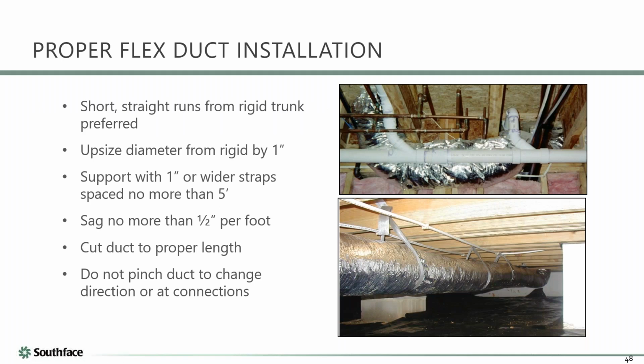Flex duct was originally intended for very short runs, like we run a trunk, we run a branch, and then the last 5 feet we connect with flex duct. And then someone said, well, let's make the flex duct get rid of the branch, and let's make the flex duct get rid of the trunk. And that's where we ended up today. And it's not the same. But if you pull it tight and support it properly, you can actually get airflow through flex duct, so it can be done right. It's very easy to not do it right.